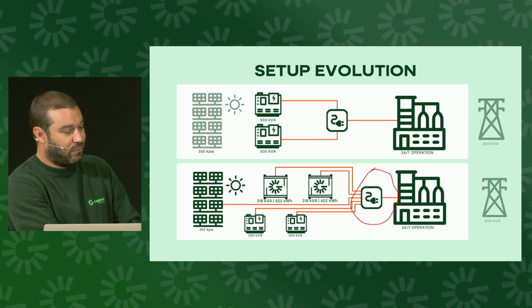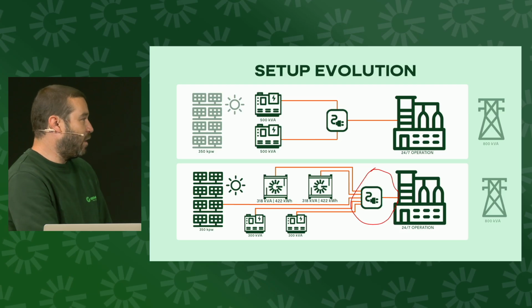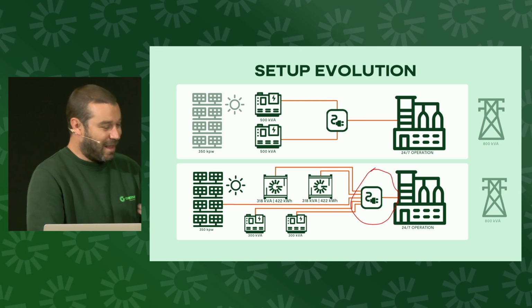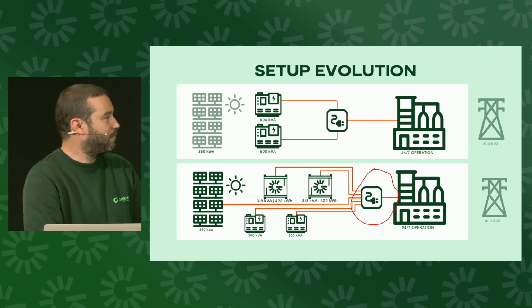And then of course the name of the game is to get as many kilowatt hours out of a litre of diesel as we can. So we run them at 80% optimum capacity, efficiency, something like that, and then switch them off when they're not needed. And with this setup, you could also utilise a smaller grid connection. So obviously they don't have their 800 kVA connection in, but if there was, for instance, a 100 amp grid connection even, you could still connect this to the common bus through some of our grid sync technology, which would enable us to force charge the systems through that device as well, or a wind turbine, but mobile wind turbines are getting there, but still not quite readily available in the market. Well, we know of one.